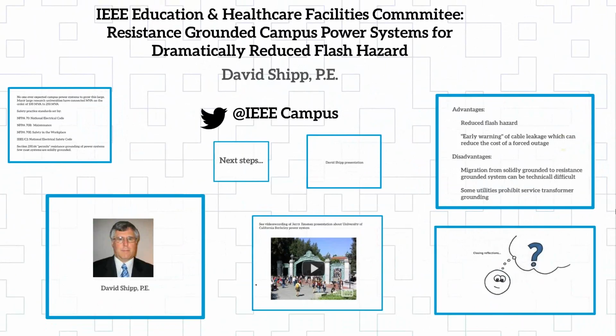Let me give you an example. The pulp and paper industry about 40 years ago went to high resistance grounded. Well, they'll have 100 MVA loads like you do, but they'll have paper machines with 100 drives on it. You trip one drive, it rips the paper, and it costs them $4 million, and the process goes down, and the like. And so the production issues. So I started saying, I can't think of a system in the emergency system, for example, in operating rooms and hospitals, that has the same type of requirement that a paper machine is. A process in the paper industry, but it's life and limb in the hospital. And frankly, I don't care about the process. I care about my life if I'm on the operating table. So I started planting seeds approximately 30 years ago out there.